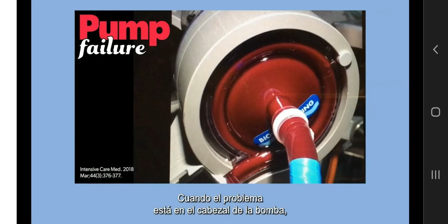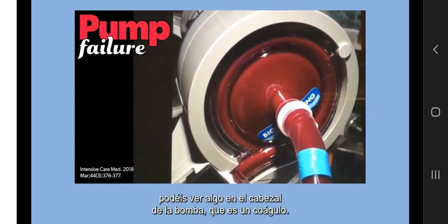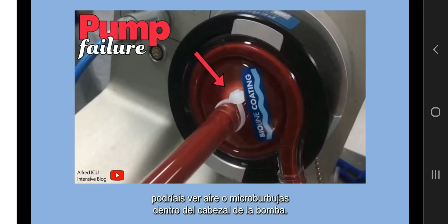When the issue is in the pump head, signs of pump failure include grinding noise and vibrations arising from the pump, particularly with disengagement and thrombosis, like in the example here. And if you slow down the video, you could see something in the pump head, which is a clot. If air enters the circuit, you could see air or microbubbles within the pump head.